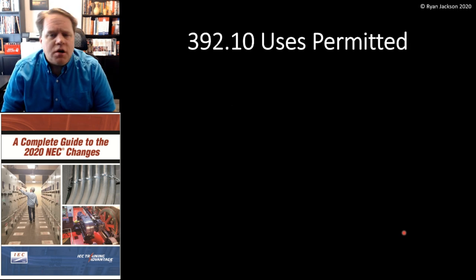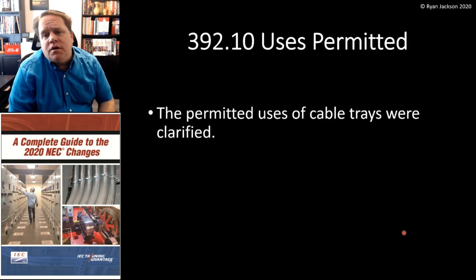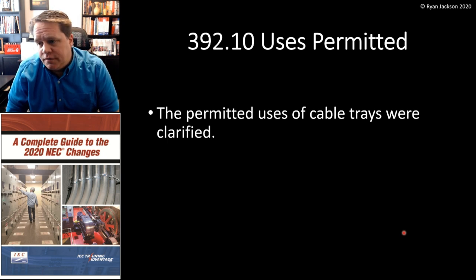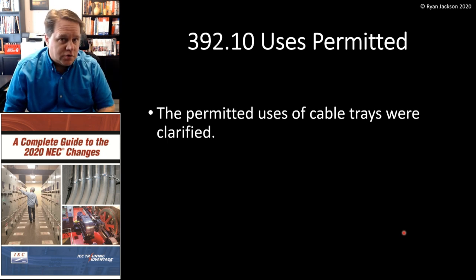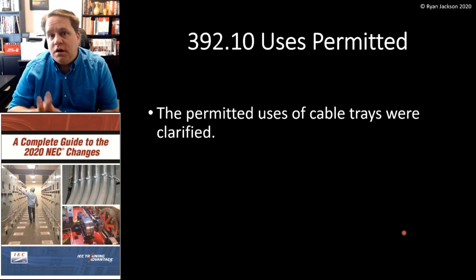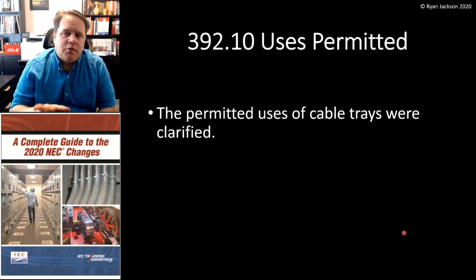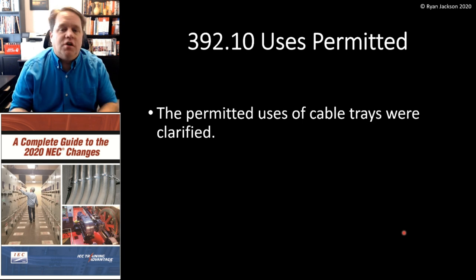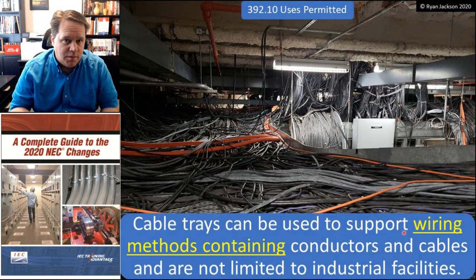392.10 Uses Permitted — the permitted uses of cable trays were clarified. Just like anything in Chapter 3 from Article 320 on up, we have uses permitted and uses not permitted. But cable tray is a bit unusual, and the reason for that is cable tray is not a wiring method — it's just a support mechanism for wiring methods.